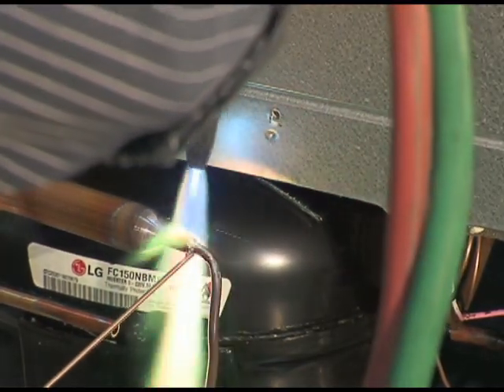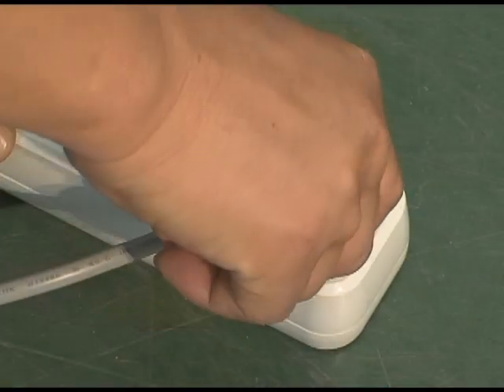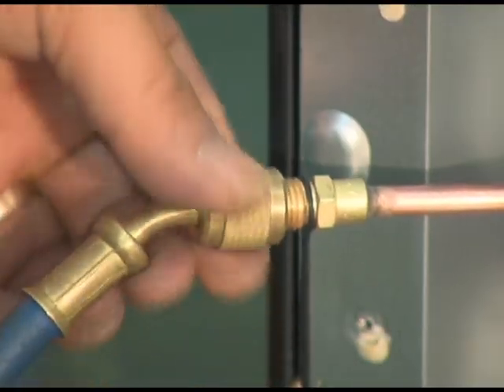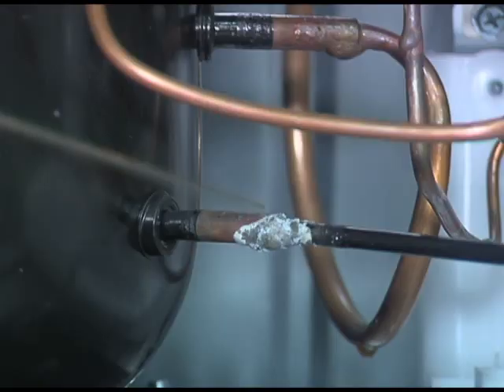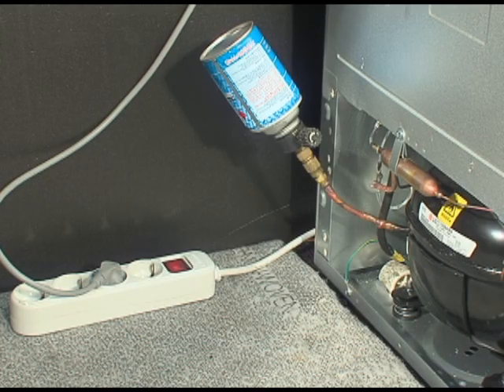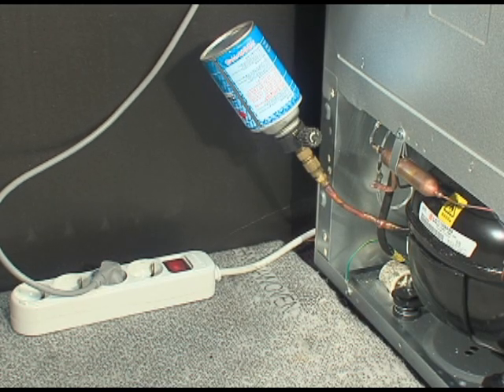Operate the refrigerator for over two hours after installing the UV dye. If there is a refrigerant leakage while operating for over two hours, fluorescent material will be leaked at that part. Turn off and discharge the refrigerant again. Weld the part where the fluorescent material was leaked. Recharge the refrigerant after vacuuming.